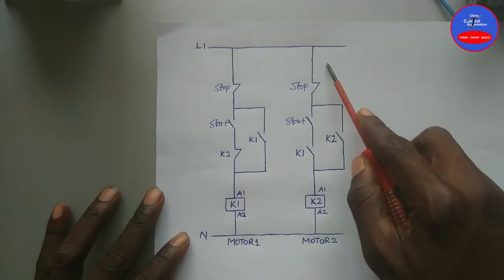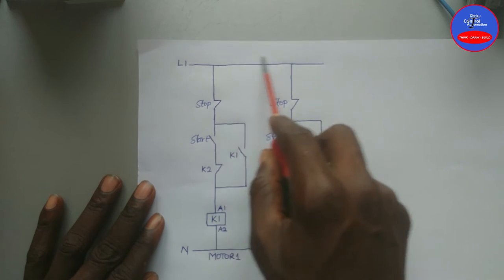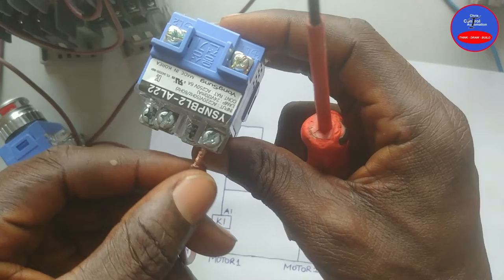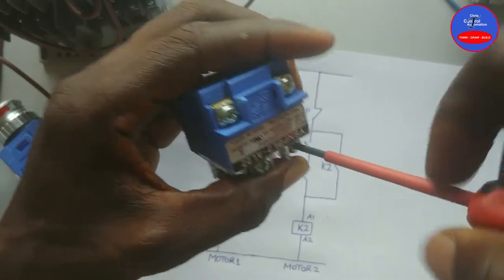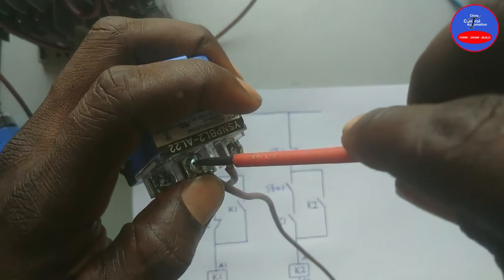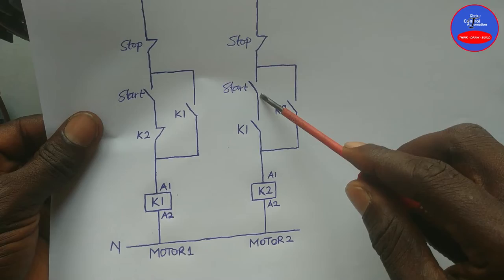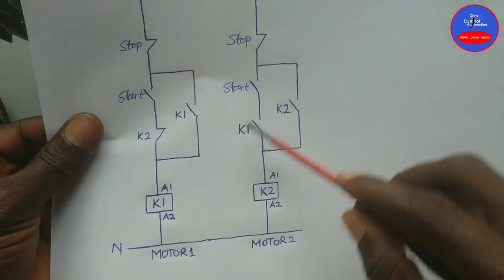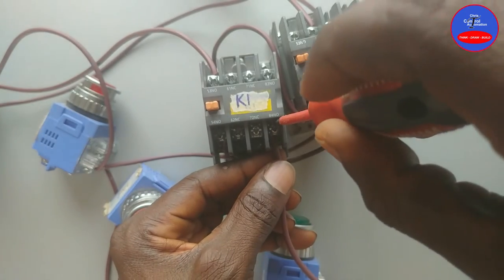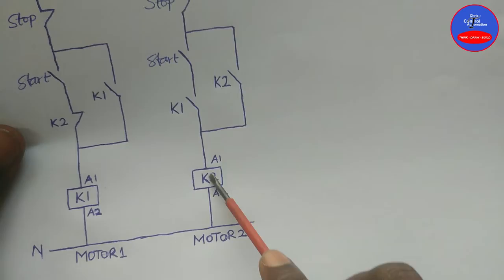We are done with Motor 1. For Motor 2, we tap from Line 1 or from the input of Motor 1's stop button to Motor 2's stop button input. From the other side of the stop button it goes to one side of the start button. From the other side of the start button it goes to one side of the open contact on K1, and from the other side of the open contact on K1 it goes to A1 of K2.